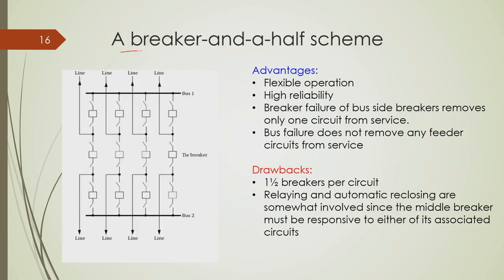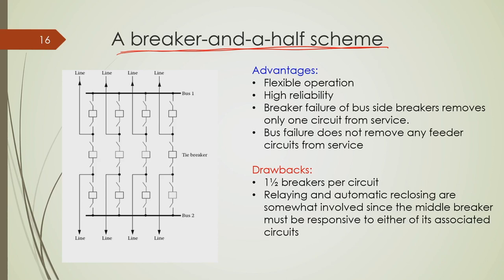Now, finally, we have another popular scheme which is called the breaker and a half scheme. This is very popular, and this is used in many substations in India. Okay. What is that scheme? In that scheme, you can see we have 3 breakers corresponding to 2 lines. So, suppose this is one feeder and this is another feeder. Now, these 2 feeders can be kept energized by these 3 breakers. Okay. So, we need 3 circuit breakers for 2 feeders.